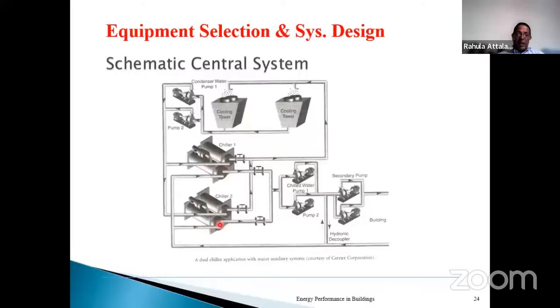It is quite customary to have multiple chillers. One reason is to be able to do the loading depending on the load requirement, one chiller and then the next. And usually we have redundancy. That is, if there is any requirement for maintenance or that kind of thing, we always have an additional chiller. That's the normal practice, what we call N+1. One unit in addition, so you can change over to that unit and attend to the maintenance work. But it is also possible to run all at part load. If we know exactly the best operating point, the combination of part load can take place. That's quite common in cooling towers. Instead of running one or two cooling towers, you run all the cooling towers, but all at part load, trying to get the maximum advantage of the equipment's part load conditions.